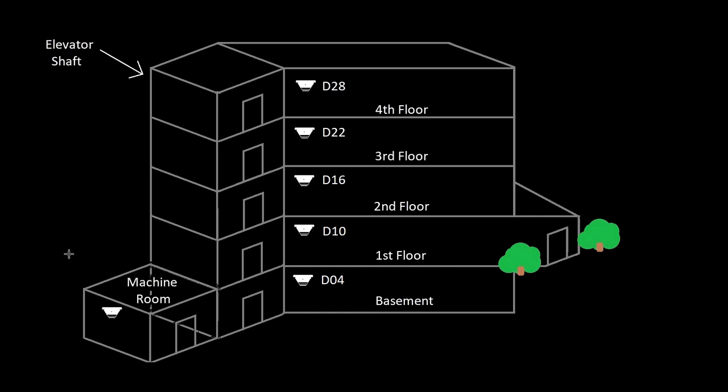That's completely dependent on the type of equipment the elevator company is using, because some elevator equipment is pre-engineered to know what floor to send the car to when they receive the fire hat signal. So just to keep it simple, some equipment only wants one relay to turn on at a time and some equipment needs you to send both signals.